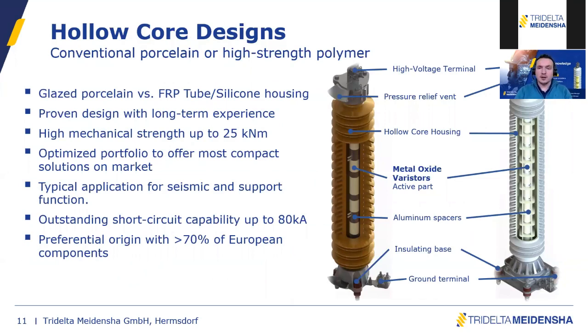Then we have two hollow core designs. One is the very conventional porcelain, which has been used for decades, at least I would say 35 to 40 years for metal oxide varistors. In that case, you see that there is a gas volume, this is why it's called hollow core design. Well, actually, this is air at atmospheric pressure inside. So the MOV stacking in the production process is placed into this tube, and we use a sealing system to prevent moisture ingress. So these are proven designs which existed before the cage design that I presented before.